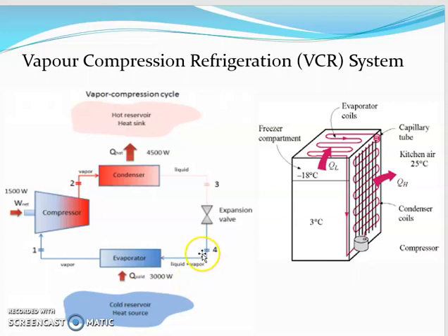First, if we start with point number 4, at point number 4, the refrigerant is at low pressure, low temperature, and it is a wet mixture, and then it passes to the evaporator, that is also referred to as the cooling coil. So if we want this space to be cooled, what does this refrigerant do? It takes the heat from this space, and so over here temperature gets reduced, and there is latent heat transformation of the refrigerant, so it gets evaporated.